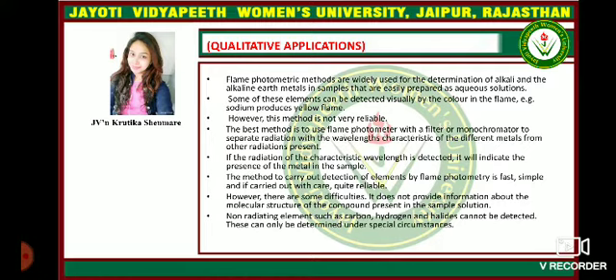The best method is to use a flame photometer with a filter or monochromator to separate radiations with the wavelength characteristics of the different metals from other radiations present. If the radiation of the characteristic wavelength is detected, it will indicate the presence of the metal in the sample. The method to carry out detection of elements by flame photometry is fast, simple, and carried out with care quite reliably.